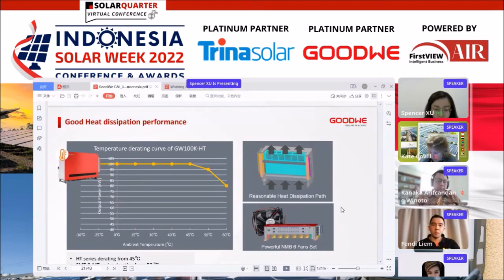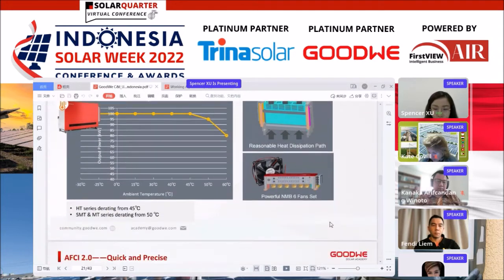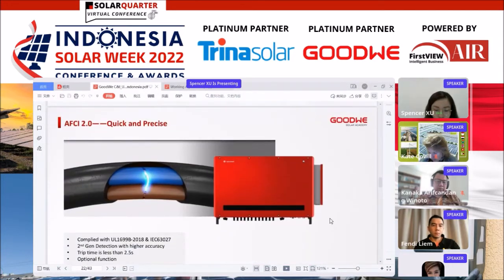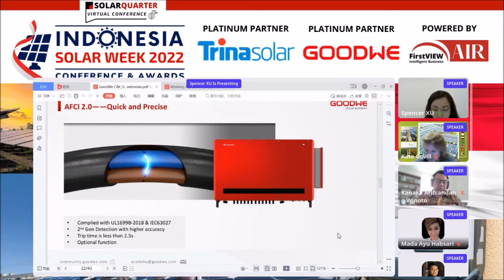And as we've mentioned before, GoodWe inverters have good heat dissipation performance because we have a very reasonable heat dissipation path, and it is equipped with 6 powerful fans. As we know, there's a hazard called arc failure, so it is very easy to trigger fire accidents. GoodWe commercial products have an optional arc failure protection with the AFCI 2 second generation level protection.